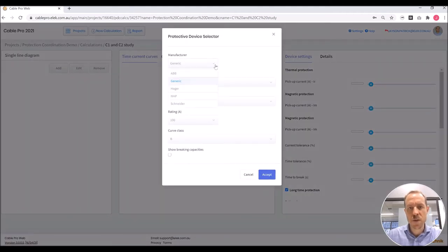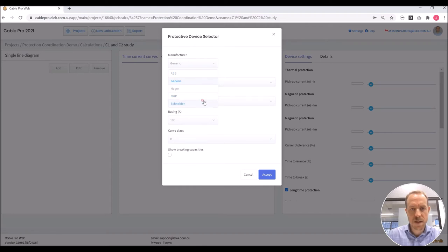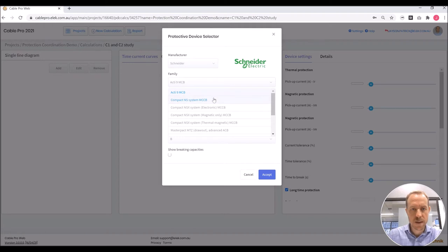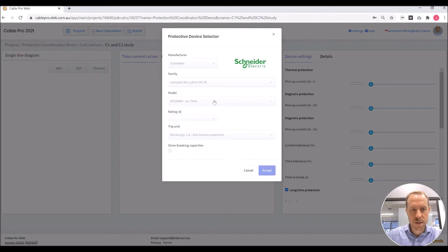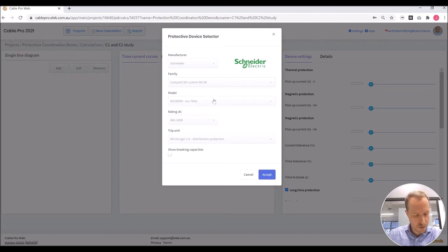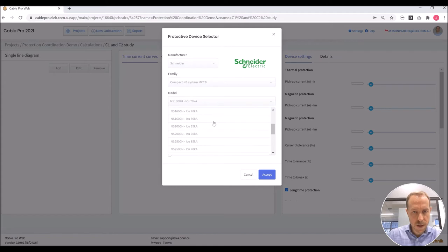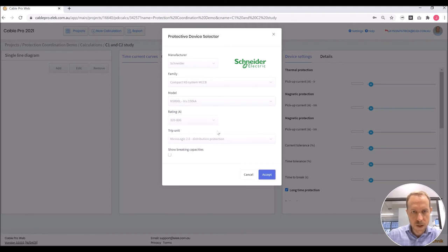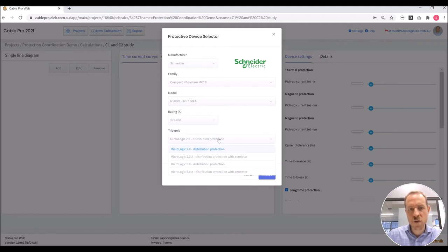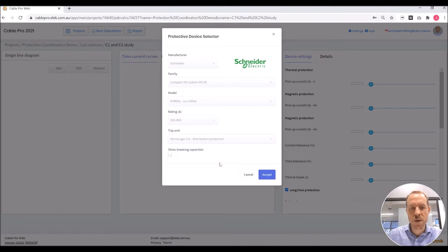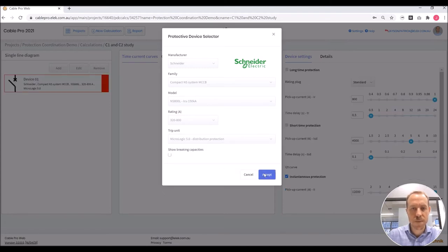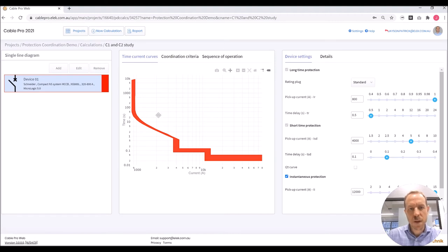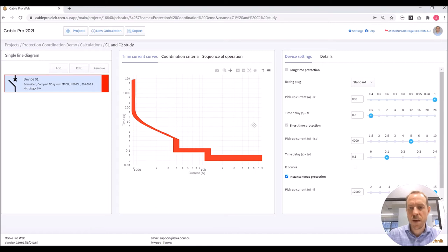First I will add the upstream breaker C1 which is a Schneider, and the family is compact NS. The model is NS800L. There we have it, the appropriate rating that we need. And the trip unit is a micrologic 5.0. We can see now that the time current curve for that device C1 is shown here, and the settings are over to the right.